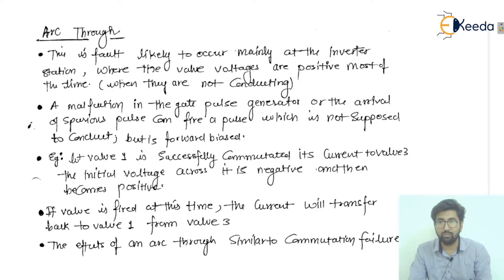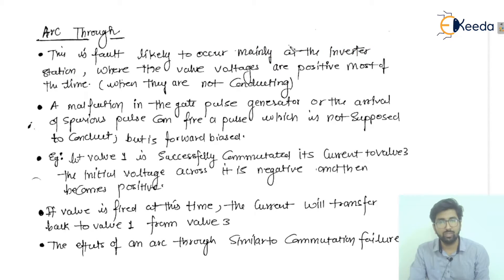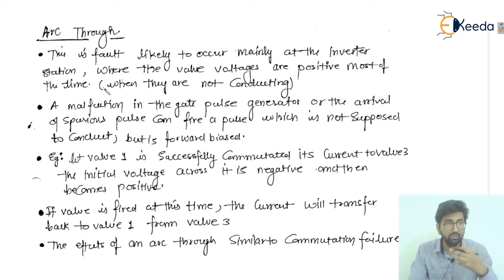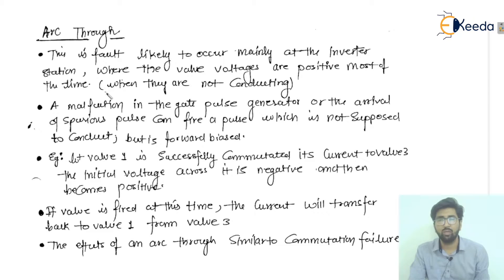The first point is: where is this fault likely to occur? It occurs mainly at the inverter stations, where the voltages across the valve are actually positive. Most of the time we will have positive voltages across the valves when this fault is occurring. This malfunction or fault is actually occurring on the inverter side.